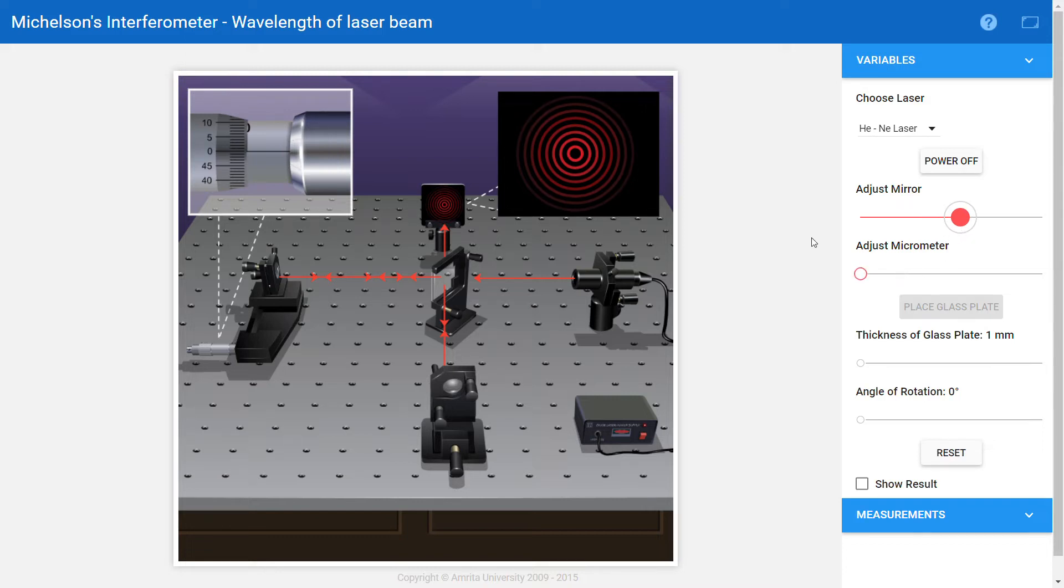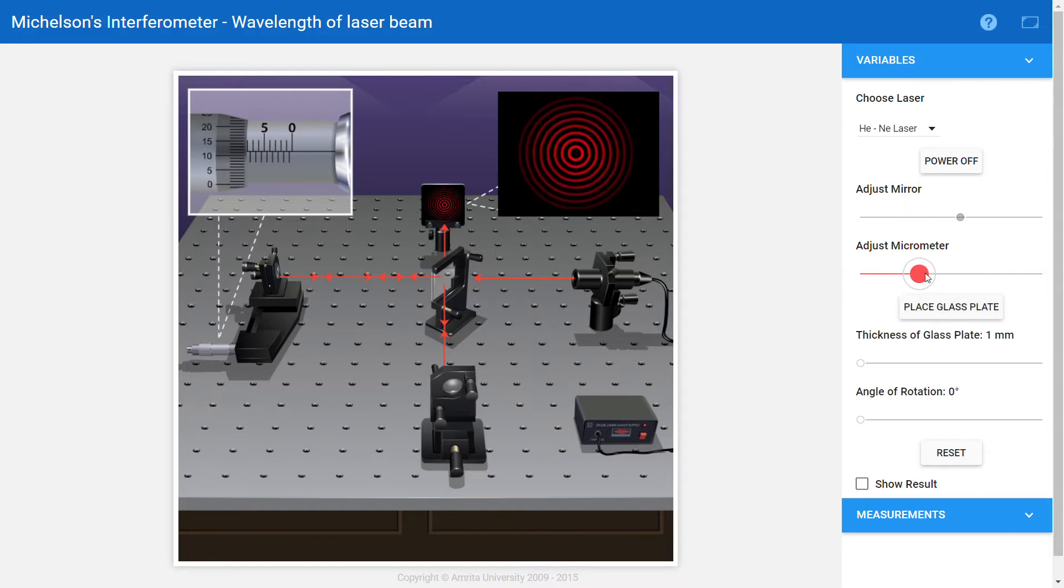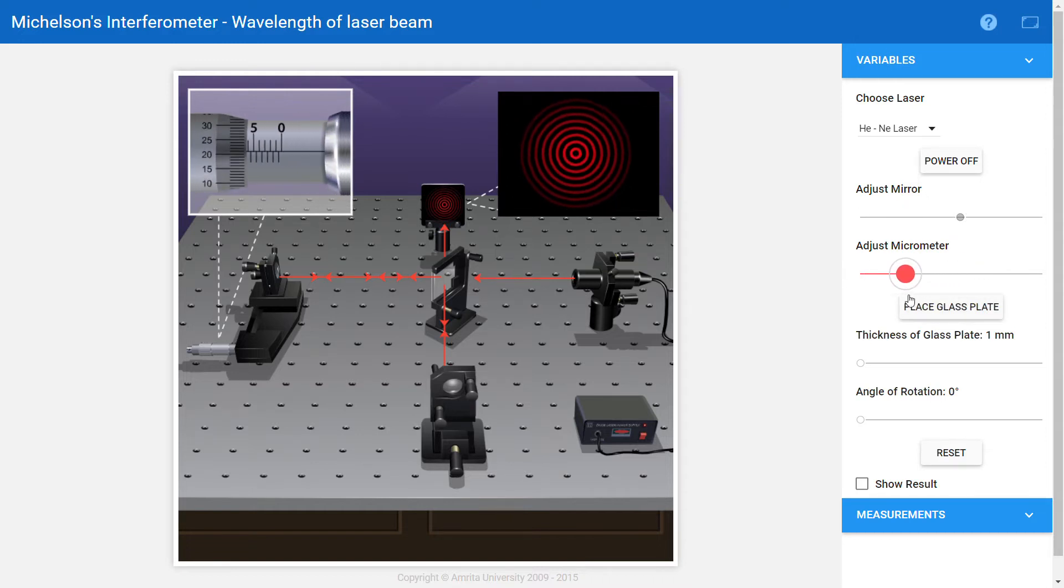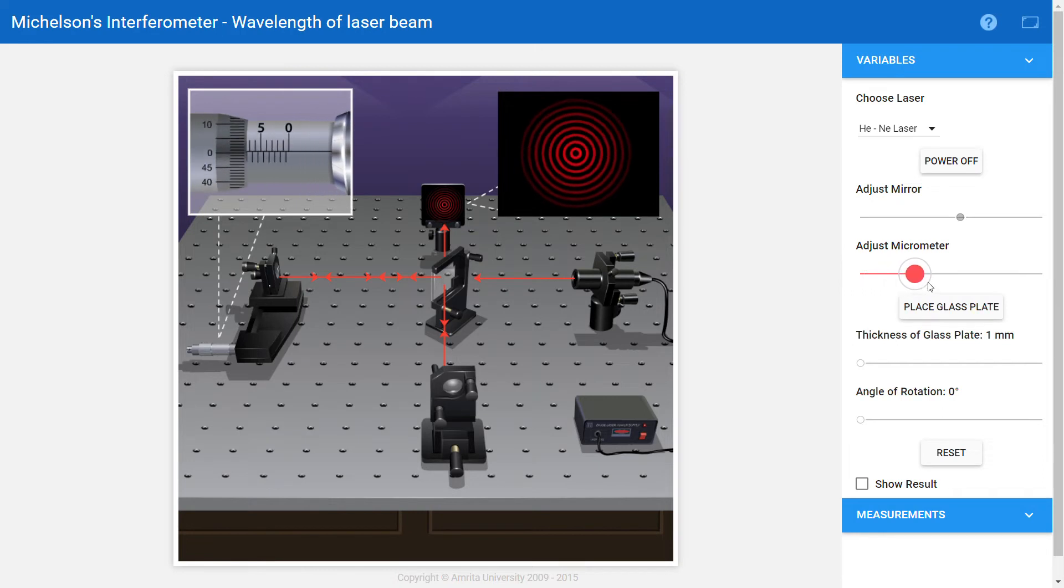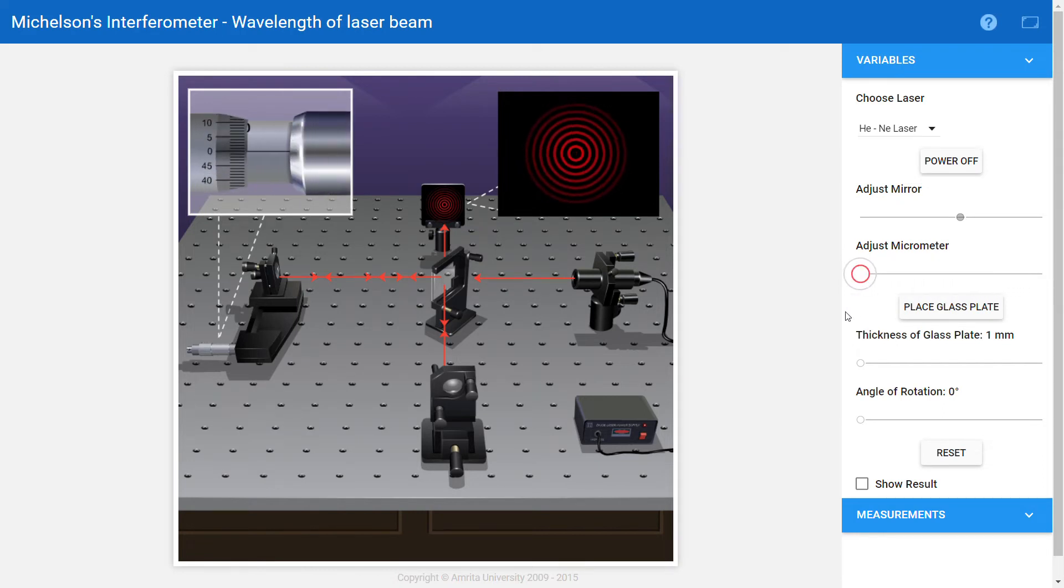I'm adjusting the mirror till I get the focused image on the screen. At this point I got the focused image on the screen and the adjust micrometer button is activated. Now I can adjust the micrometer to introduce path difference between the rays and produce interference fringes.